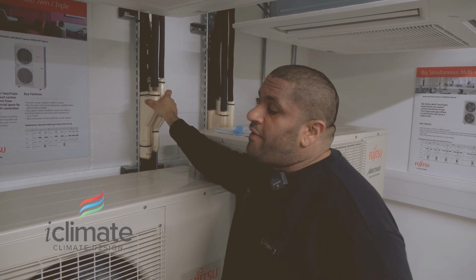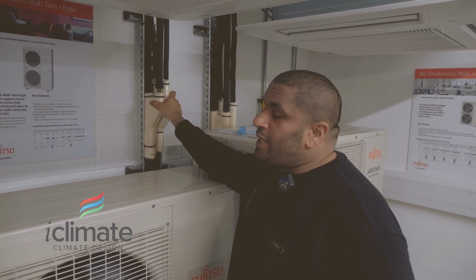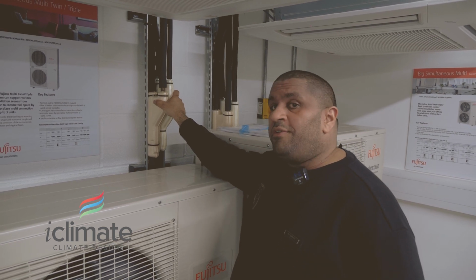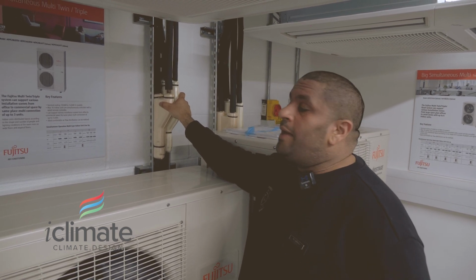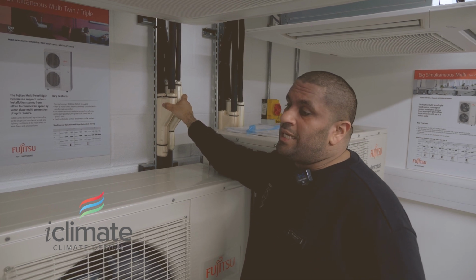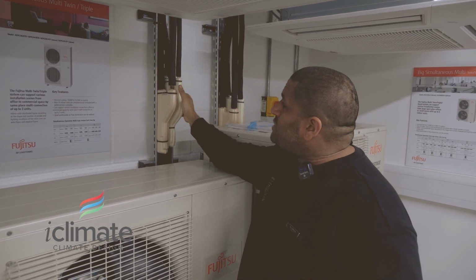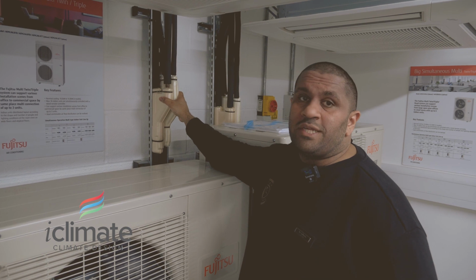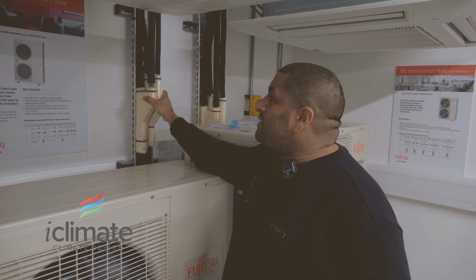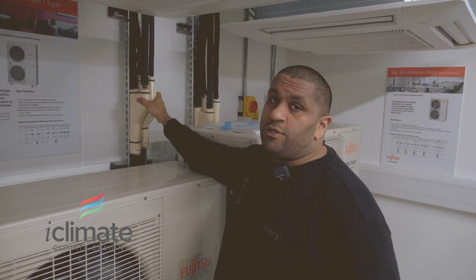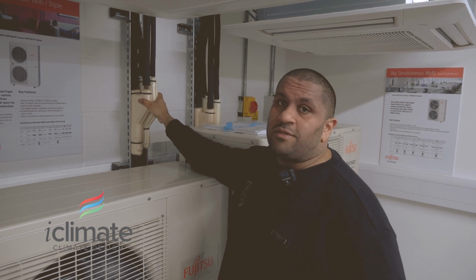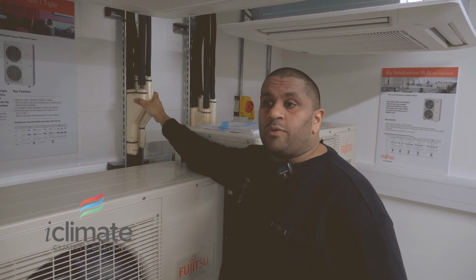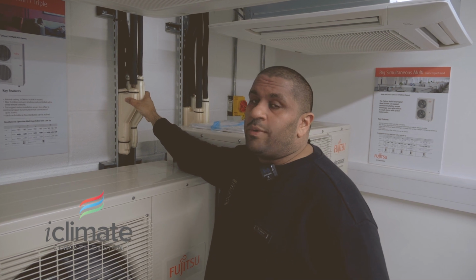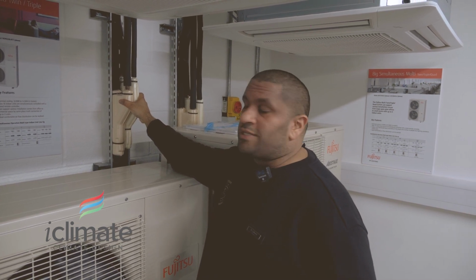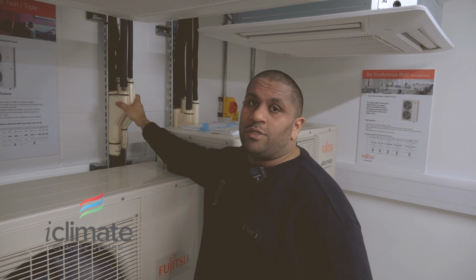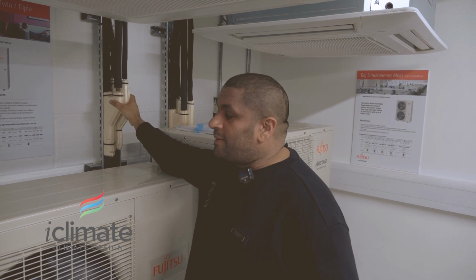So if you have a very large domestic property and you wish to have one outdoor unit with one set of pipes and you're going through a refurb, then the VRF can be suited to you. But typically the VRFs are installed in commercial spaces. So you will see these ref nets within commercial building risers or within ceilings serving a large number of indoor units at a very high capacity for cooling and heating. So it could be multiple office floors, hotels, or commercial spaces such as factories and stuff like that. So light commercial or very large domestic is the application for the VRF.